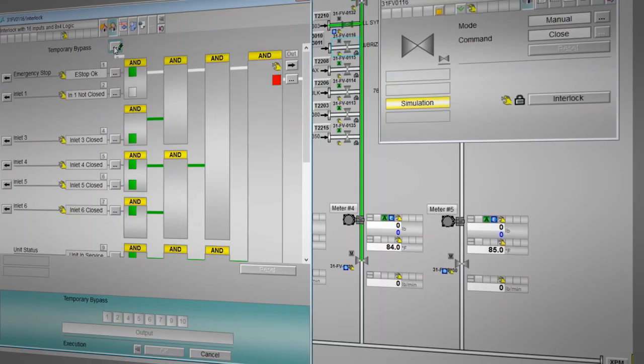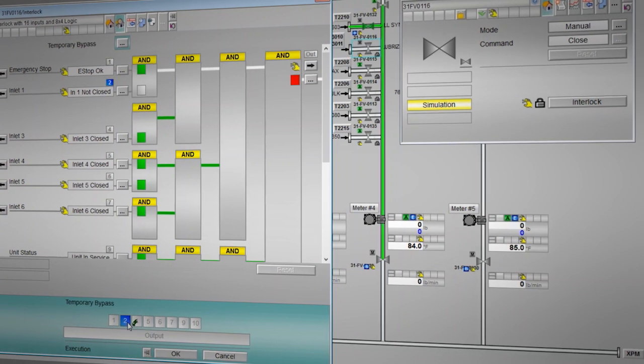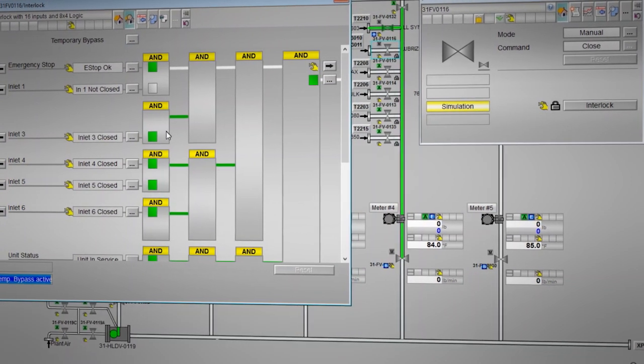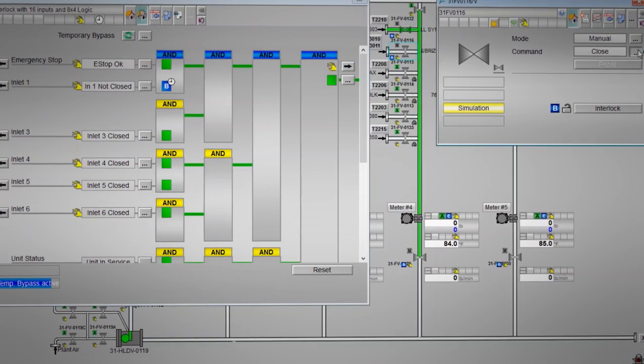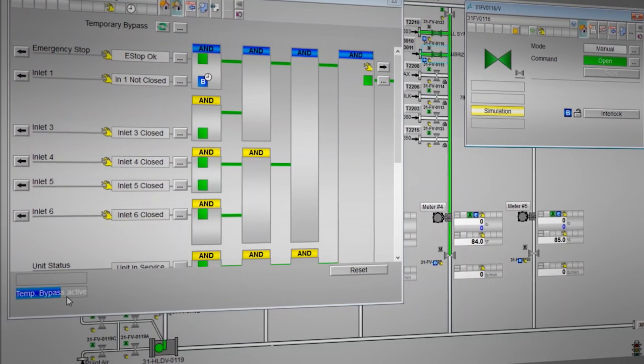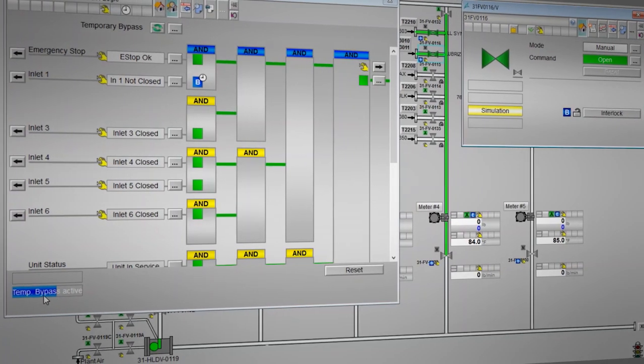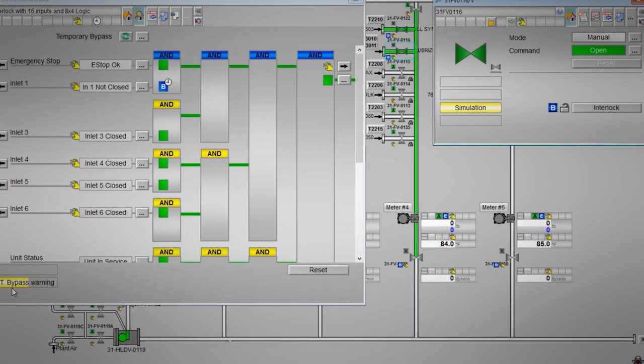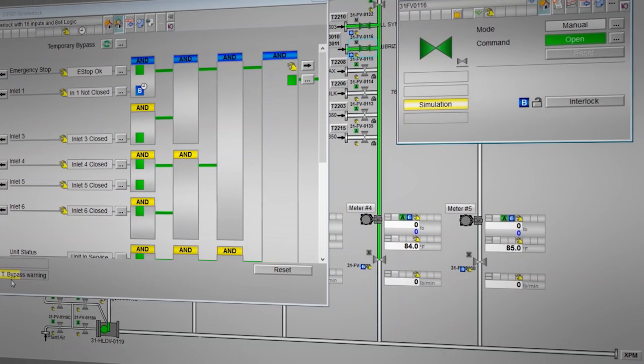at the plant. The Siemens Industry Library is a set of special blocks for specific industries. One of the things we like about the Industry Library is the 8x4 interlock block. It allows us to do a little bit more complex interlocking, and it also has a timed interlock feature for bypassing that allows you to have a bypass work for a certain period of time, a predefined time, so that you can get through a transfer or you can finish a shift, and then maintenance can go back and fix that item without having to remember they have to unbypass an interlock.